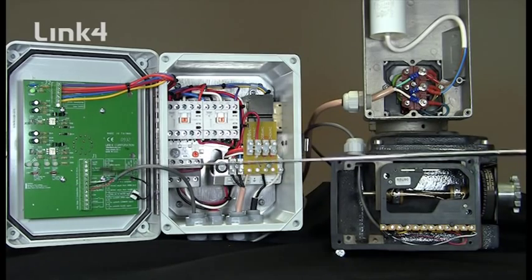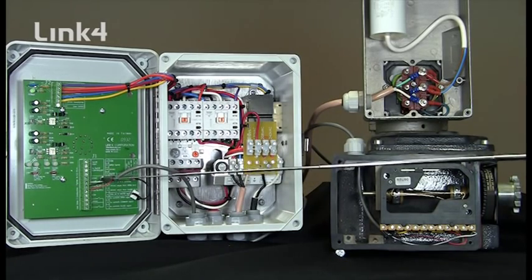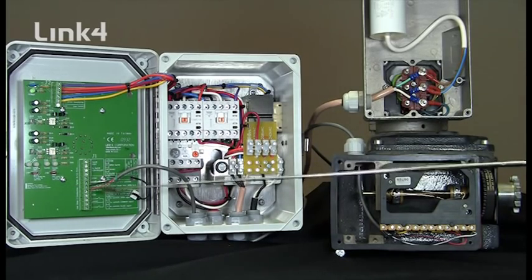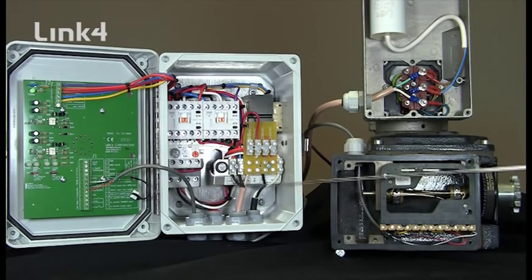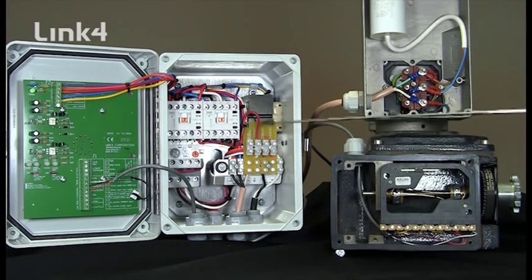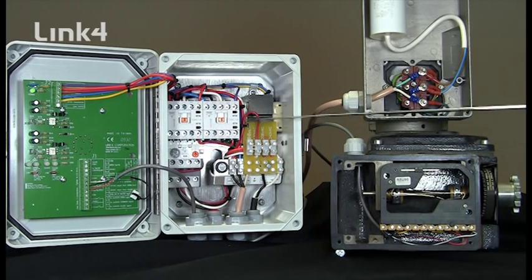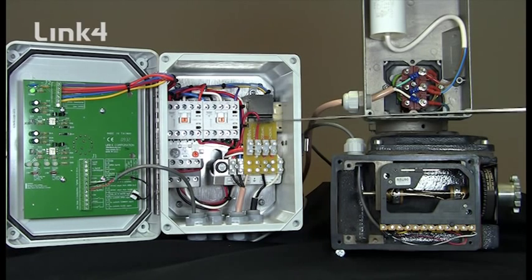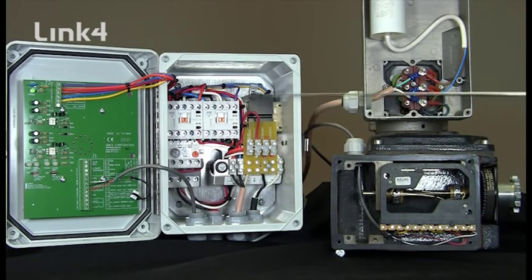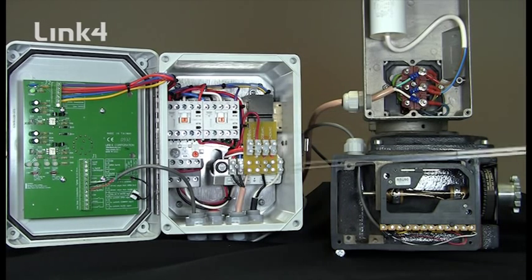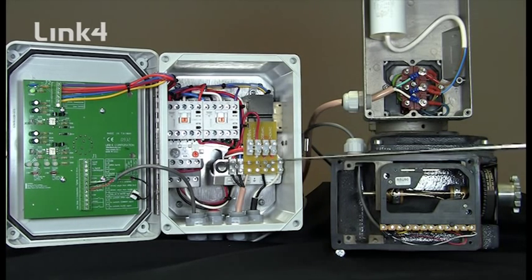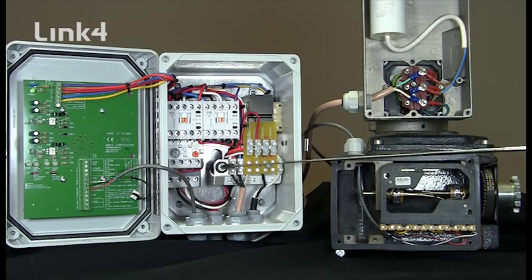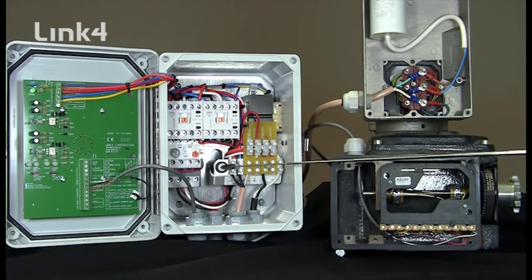We have our 3 wire limit connection. We have our motor connection. And we have our voltage selector wire which determines what input voltage will give the 24 volt AC out. We have a fuse for motor and load protection on the input side of the line voltage.